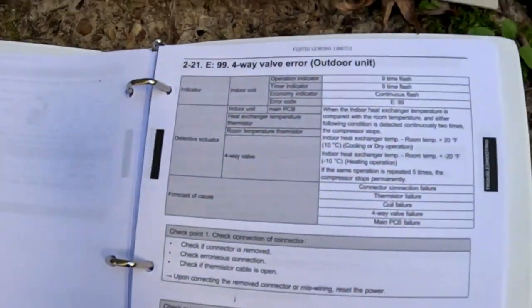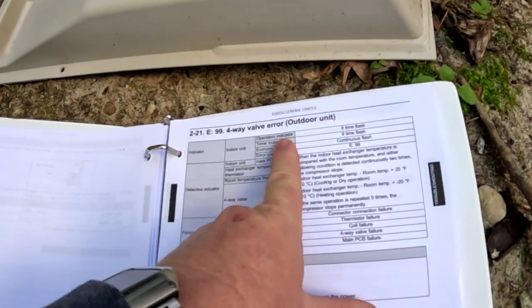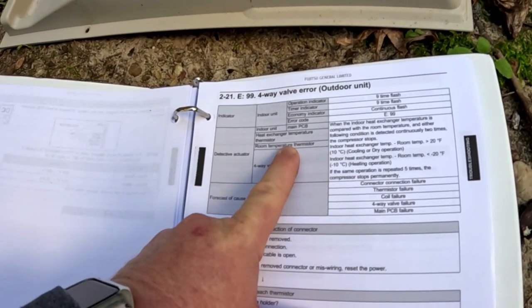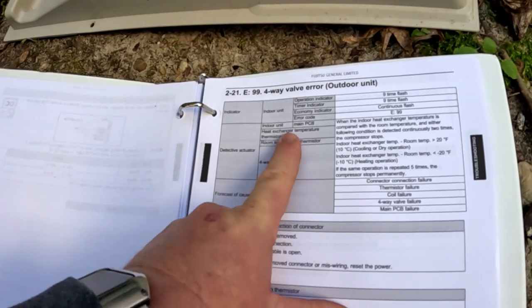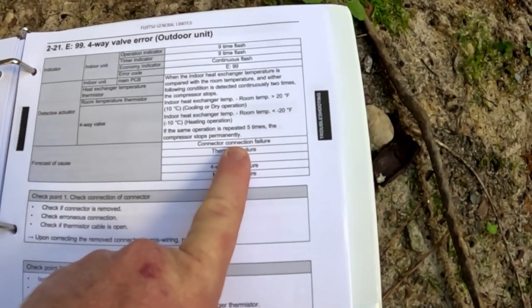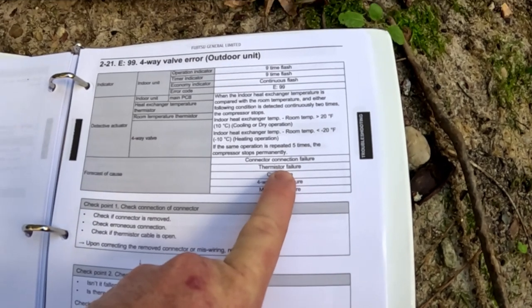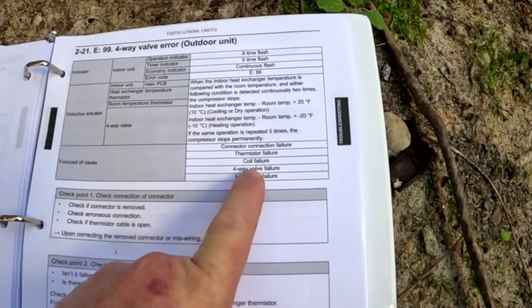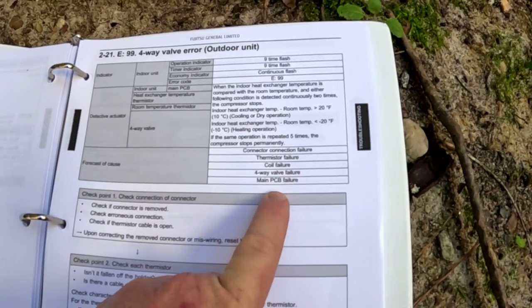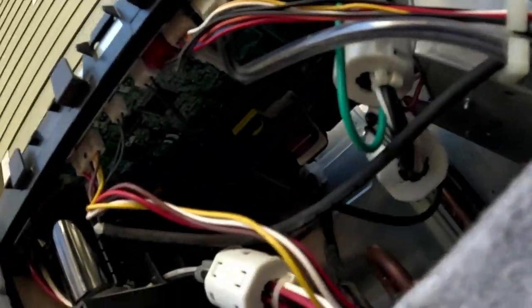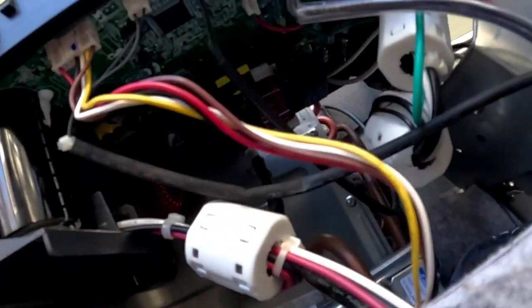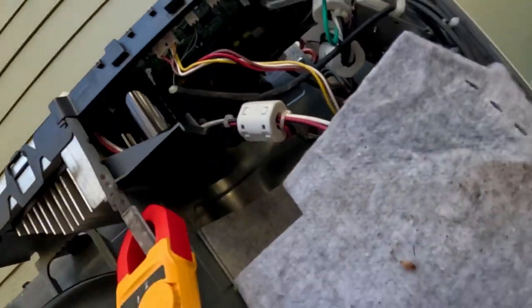Alright, so for this 4-way valve, it goes through the flashes that you're going to see: heat exchanger thermistor, room temperature thermistor, 4-way valve, main PC board. What your possible issues might be: either a connection failure, thermistor failure for the indoor temperature, indoor coil, maybe a pinched wire, coil failure, 4-way valve failure, or the main board. There's no lights on this board that I can see anywhere looking around. Nothing flashing. I don't see where there's a board light on it anywhere that I can tell looking up in there.